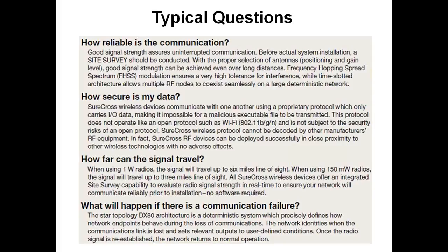Another question that typically comes up is, what happens if I lose my RF link? The way our system's set up, we have a deterministic system which will allow you to predefine what you want the outputs to do. For instance, if it's an analog signal, 4 to 20 or 0 to 20, you can park that at a specific value once you lose the link. As soon as the link is reestablished, it'll come back and everything will go back to normal mode.